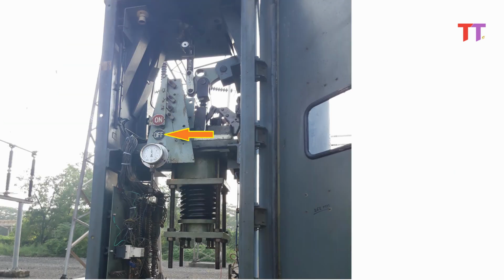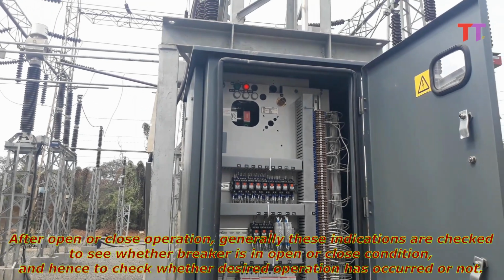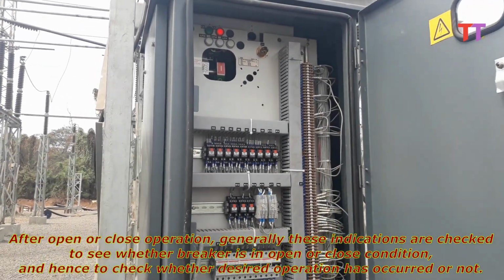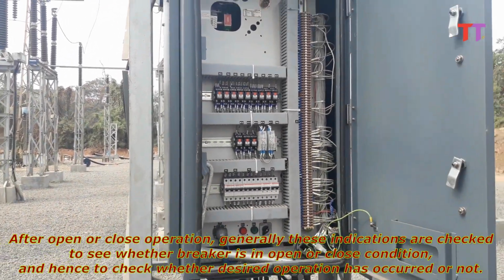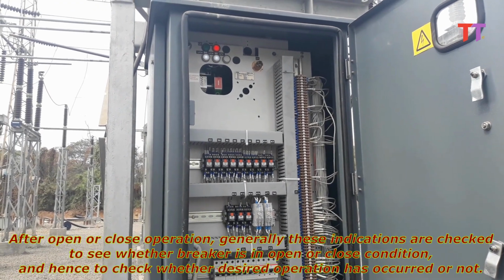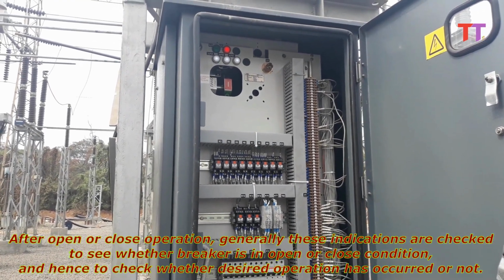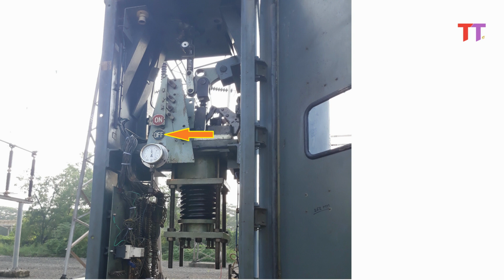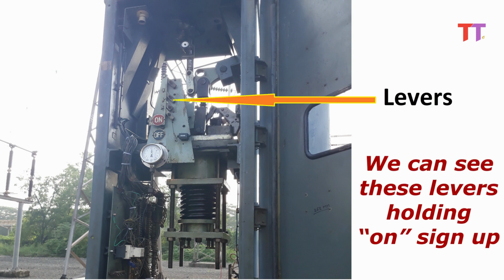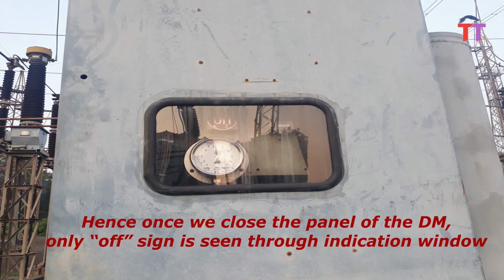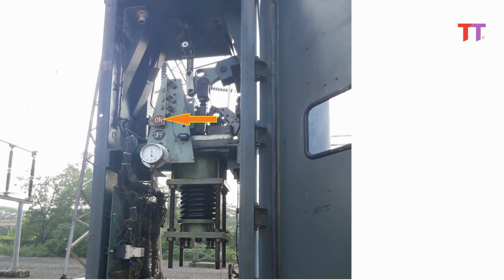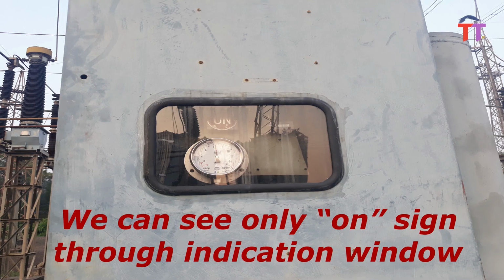These are on and off indications. After open or close operation, generally these indications are checked to see whether breaker is in open or close condition, and hence to check whether desired operation has occurred or not. Here we can see breaker is in off condition, meaning open. We can see these levers holding on sign up. Hence once we close the panel of the DM, only off sign is seen through indication window. In close condition, this on sign will slide over off sign with the help of the levers, and we can see only on sign through indication window.